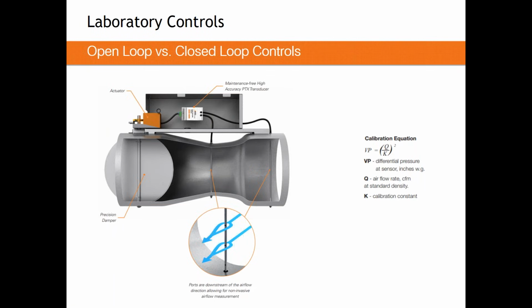So with any method of measurement, you are susceptible to contamination. To give an extreme example, if you were to take a Kleenex inside the high accuracy terminal you see here and wrap it around that post, it would no longer measure airflow very well at all, if at all. Any method of measurement is susceptible to this. So all measuring valves may need to be inspected and may need to be cleaned. Some styles are more resistant to contamination, but they are all susceptible.